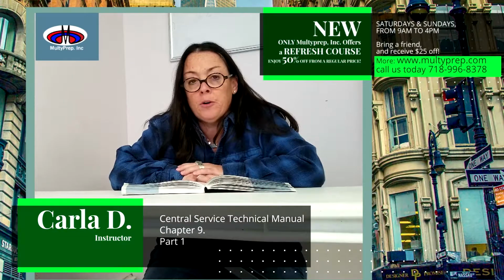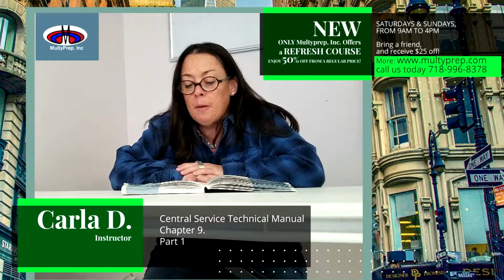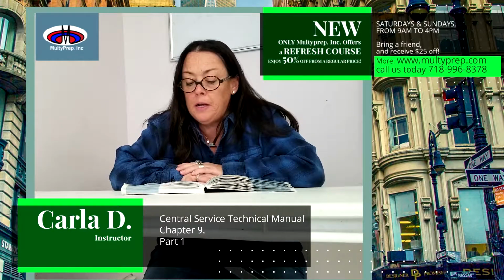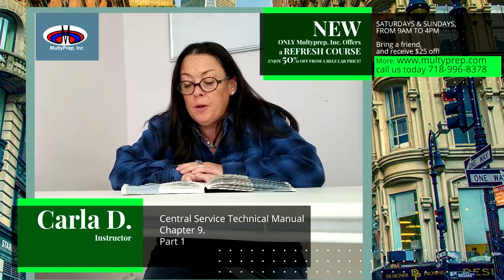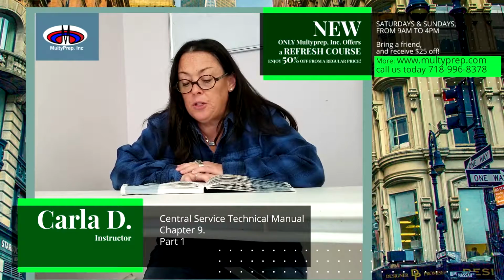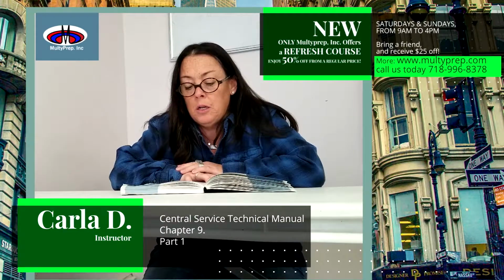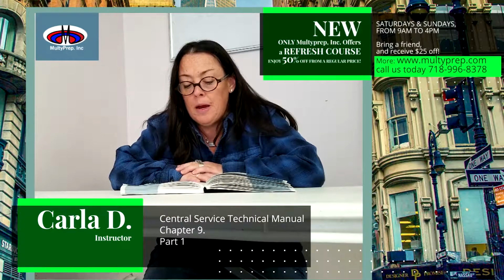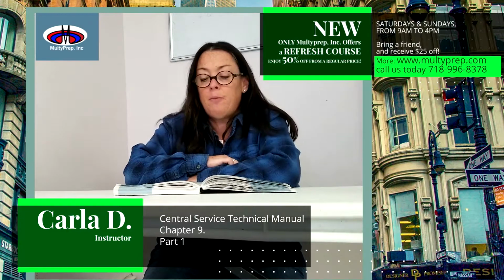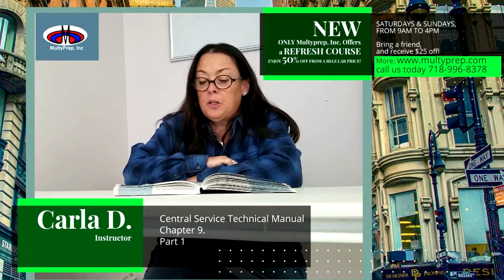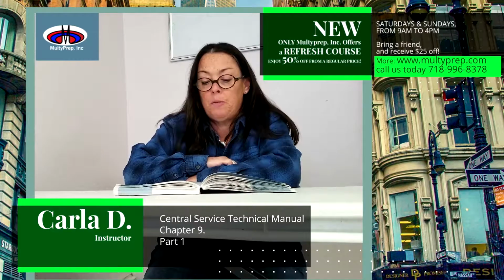Chlorine is an intermediate level disinfectant that is commonly used for the treatment of water and sewage. Chlorine, a member of the halogen family, may be found in CS departments as a hypochlorite solution, often recommended for biohazard cleanup procedures. However, chlorine is not considered a disinfectant of choice for CS due to its corrosive qualities. Metal instruments subjected to chlorine may have their finishes damaged by exposure to chlorine solution. Figure 9.8 at the bottom of page 166 reviews the basic information about chlorine.